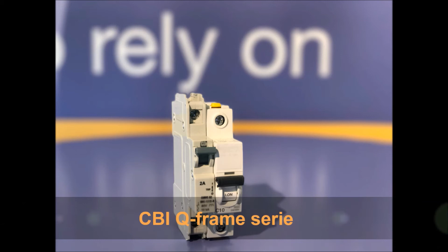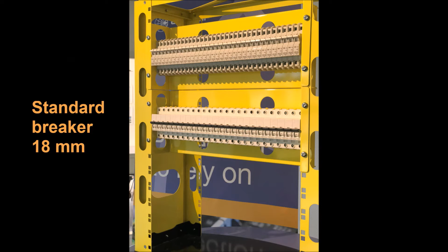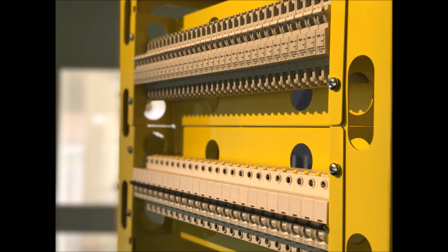Okay, when looking at the Q-frame, in particular, if you have a standard DIN rail mounted breaker beside it, the main feature is quite visible. The Q-frame has a width of only 13 millimeters compared to a standard DIN rail mounted breaker, which has a width of 18 millimeters. This means that with the Q-frame, you can have 30% more distribution points on the same space compared to a standard breaker, making it perfect for applications with space constraints. Since the Q-frame is a hydraulic magnetic circuit breaker, stacking them together is not a problem since heat is not an issue.